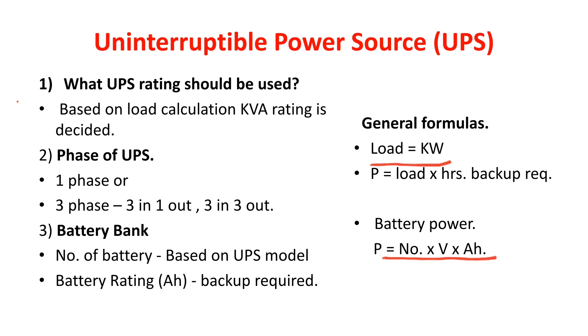Now coming to the UPS connections. We require an input panel for controlling the input power supply of the UPS. Power supply to the UPS is given from an AC source, so we need some controls to connect, disconnect, and overcurrent protections on the input side. We also require an output panel to control the output power coming out from the UPS. From the output panel, output power is distributed towards the distribution boxes where different loads are connected, where you need UPS supply.